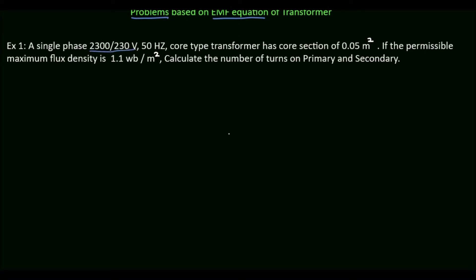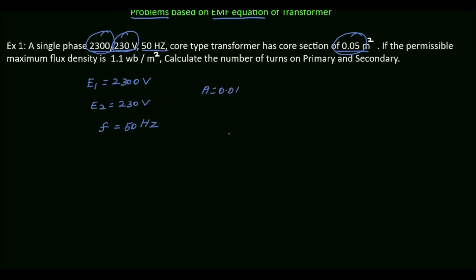The problem: a single phase 2300 by 230 volt, 50 Hz, core type transformer has a core section of 0.05 meter square. Here, 2300V is the EMF induced in the primary side, so E1 = 2300V; 230V is the EMF induced in the secondary winding, so E2 = 230V. The frequency is 50 Hz, the area is 0.05 m², and the permissible maximum flux density BM = 1.1 Weber per meter square. We need to calculate the number of turns on the primary N1 and the number of turns on the secondary N2.